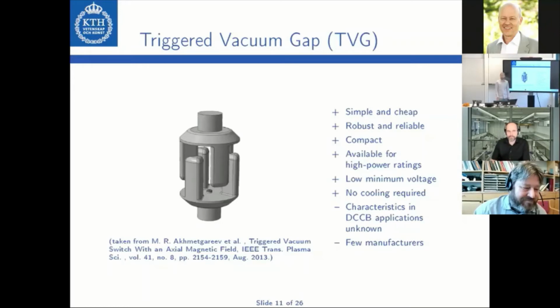Okay, but why didn't you choose, for example, a simple spark gap or something like this, which you could also buy off the shelf? Why vacuum gap? I mean, let's say you would have just had a triggered spark gap in air without any kind of pressure chamber. Then it can be expected that the dIdt and dVdt capability of this device is lower, or so to say, the dielectric withstand capability after the current zero is better for the triggered vacuum gap. This is, of course, something we have not analyzed in experiments, but this is something that we expected. Therefore, we thought that this triggered vacuum gap, because of its superior dielectric property, is an ideal candidate for this application.